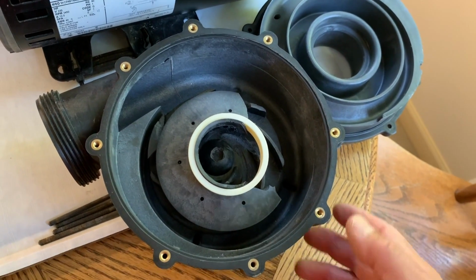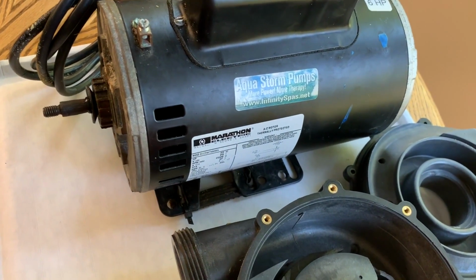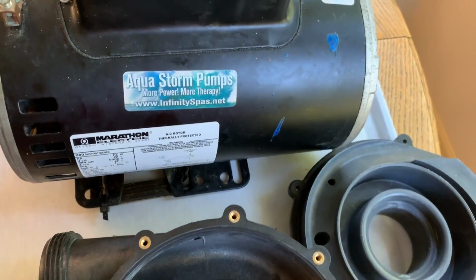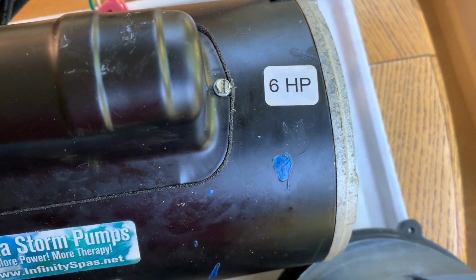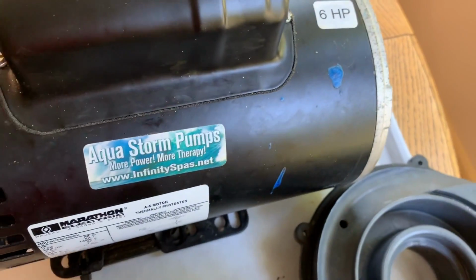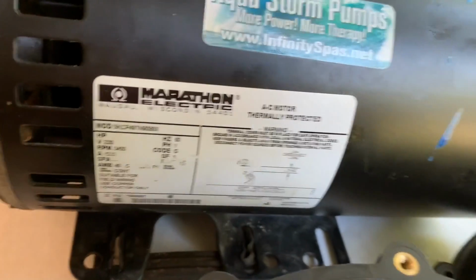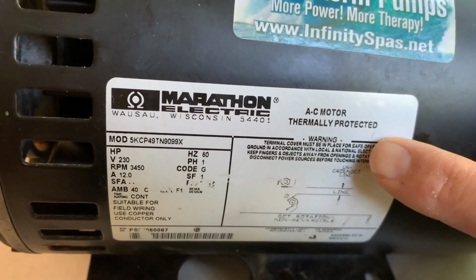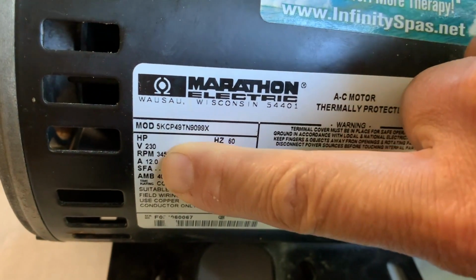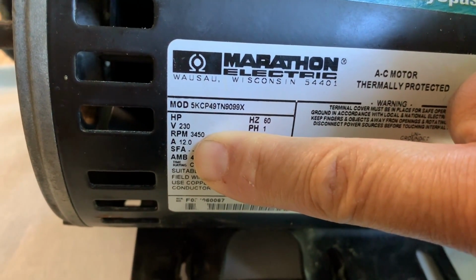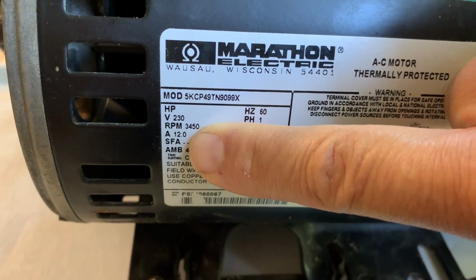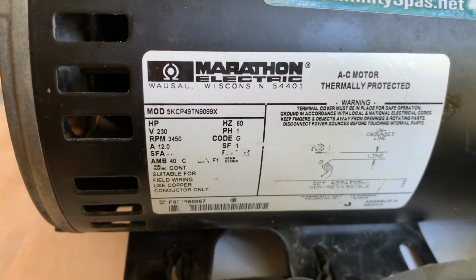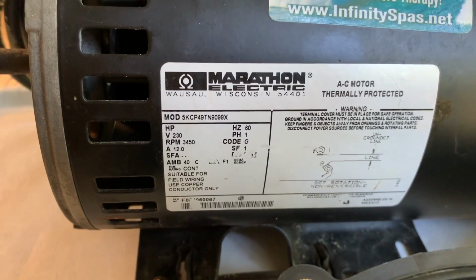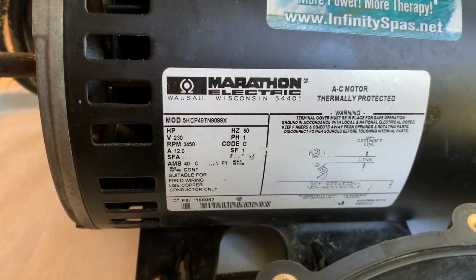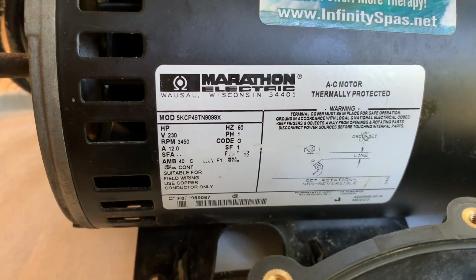So I needed to find a replacement wet head that will bolt onto the same pump as a replacement. One thing that I've learned is that this little sticker on the motor here, which says 6 horsepower, really doesn't mean anything. What you have to do when you're looking for a replacement is look on the actual motor sticker here and look at the amperage rating of the motor here. This is 12 amps. And there are several sources where you can look on the internet to find replacement wet ends. And that 12 amp rating translates to 3 horsepower, not 6 horsepower.